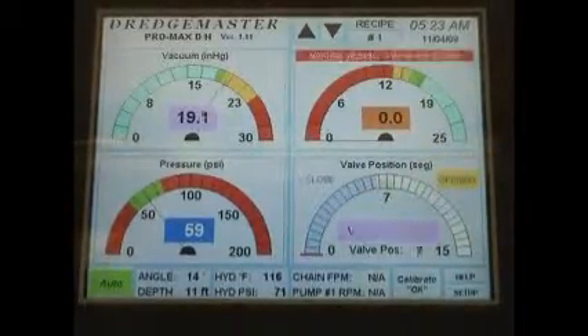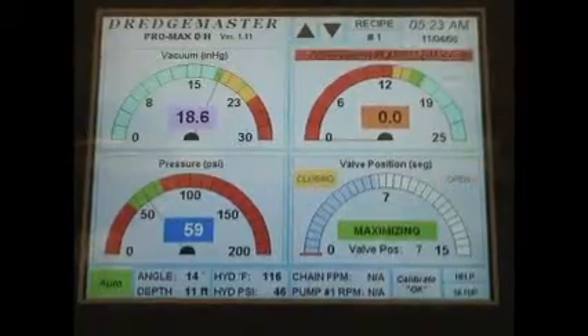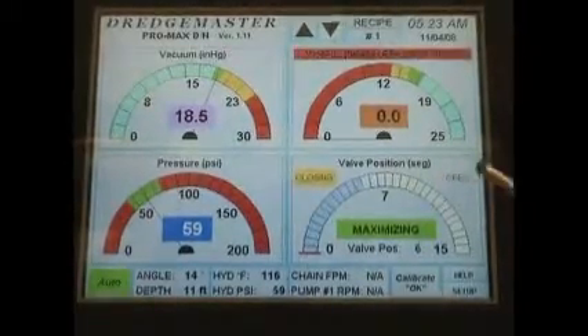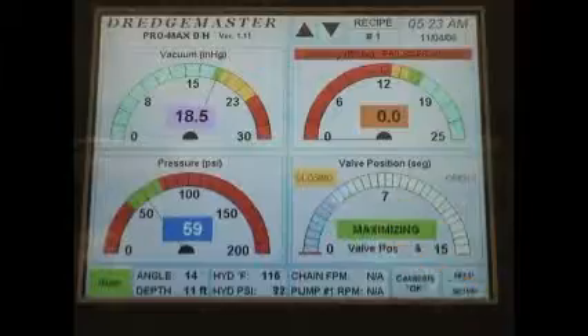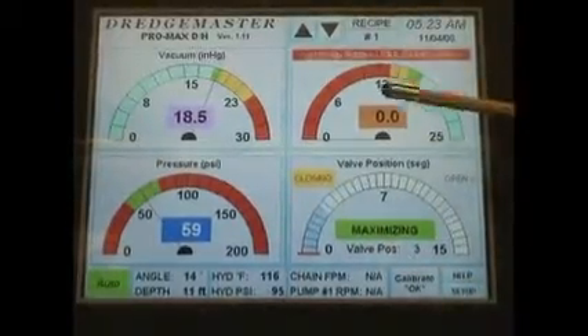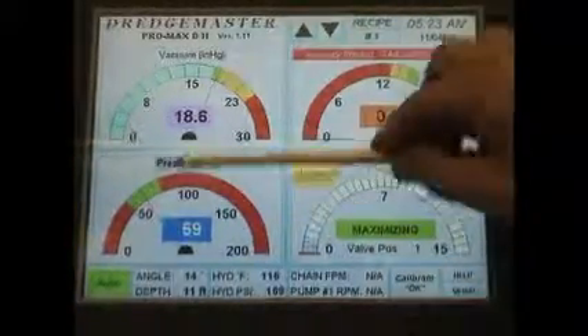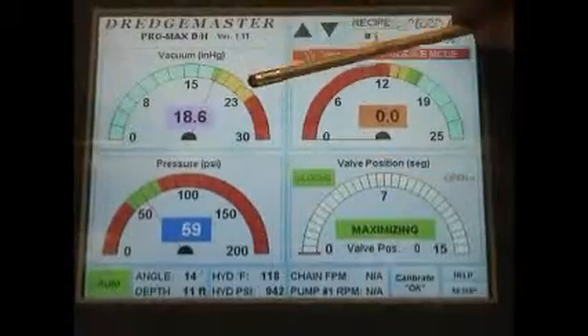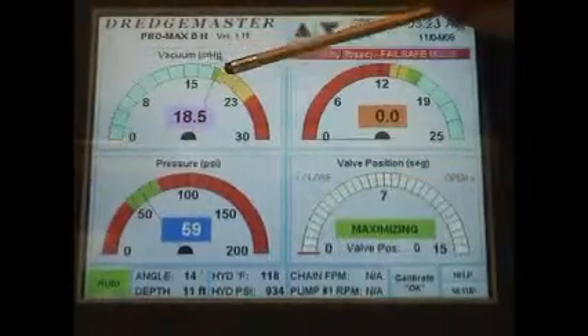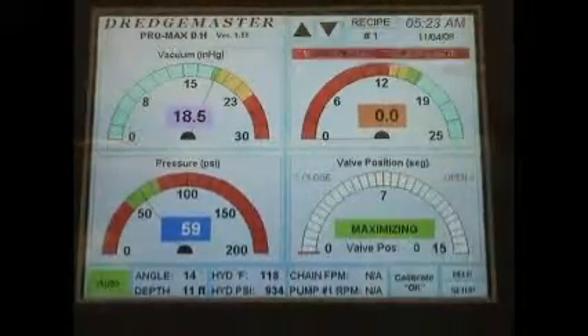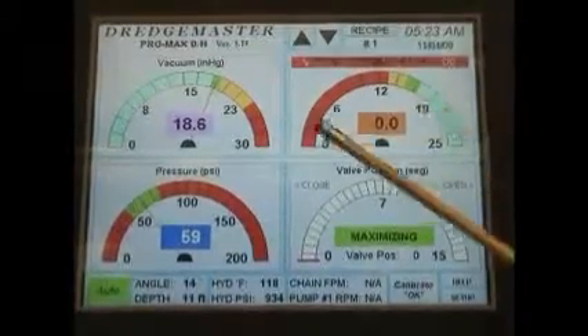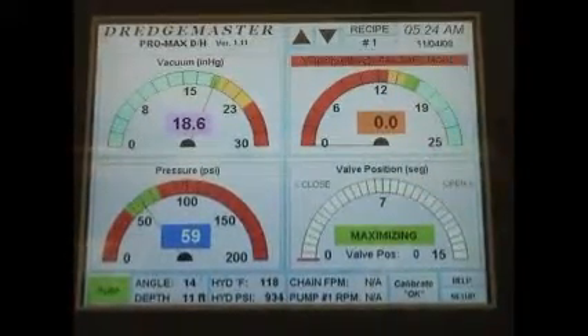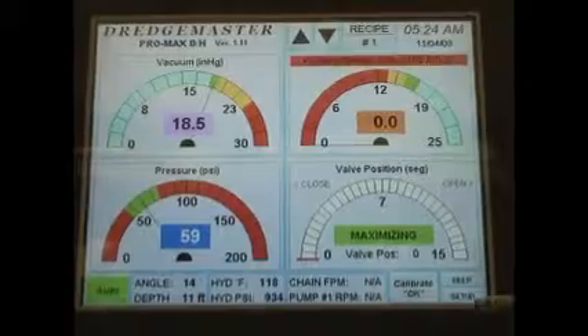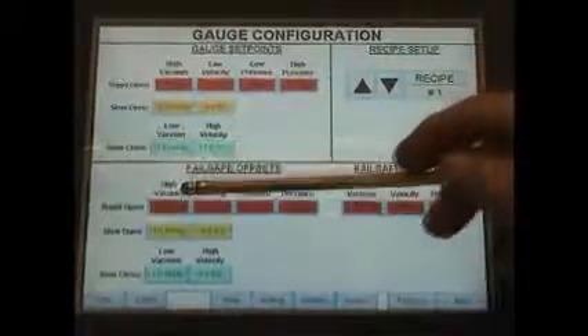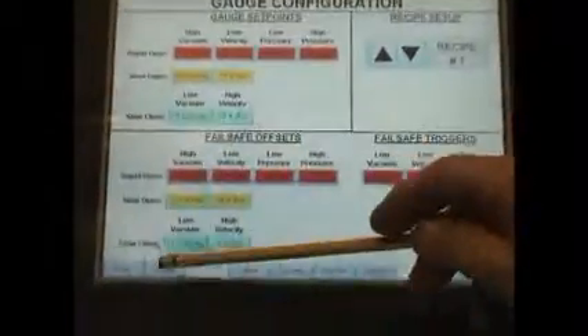If we get the velocity or vacuum drops, we get back in the green zone, then it will again close up. So we lost a third element here, so that is the reason why we're narrowing this band up a little bit, to give a little more protection, because we don't have the velocity meter to back us up in this particular instance. To change our fail-safe offsets, you simply would touch the square.